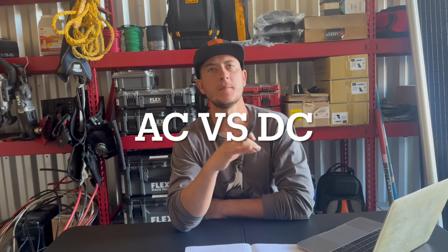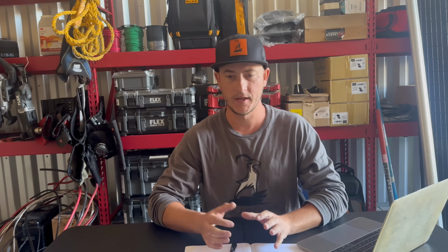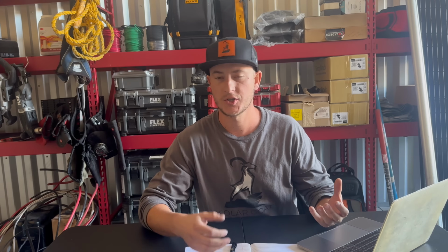This is one of the most common subjects that I have coming up with new electricians going into solar. When it comes to AC and DC, you have the two inverter types: microinverters, string inverters. Kind of summarize it down to that. Microinverters plug into the back of the solar panel, generally on the roof, and then from the microinverter you have 240 volts AC and you have parallel connections.